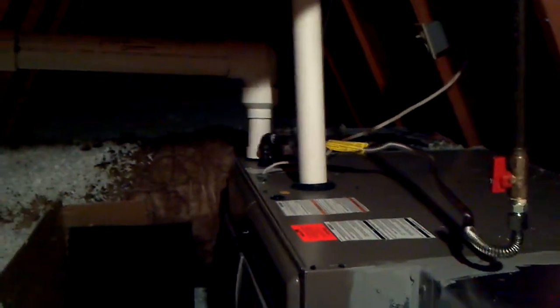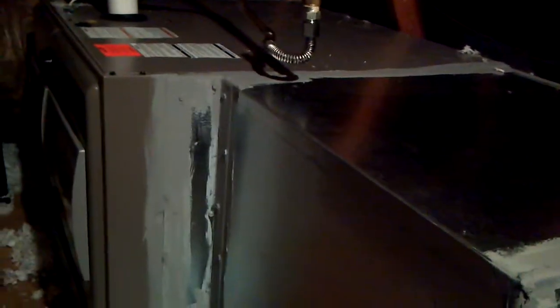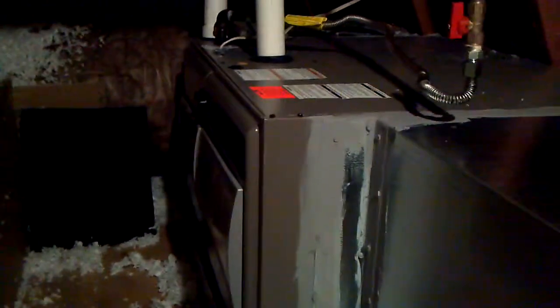So that's a recap on some home performance work. This is, of course, a high efficiency furnace. You'll see the pipes coming out the top. There's a condensate drain line that goes out. Small things like that. The horizontal application has an emergency drain pan in case we have any kind of condensation leak. And this yucky, really bad looking stuff is called mastic duct sealant. Yes, it is ugly, but it's the only way to seal up ductwork when you're dealing with these plenums, etc. When we're dealing with the entire system, we use AeroSeal, which you can find on our website.